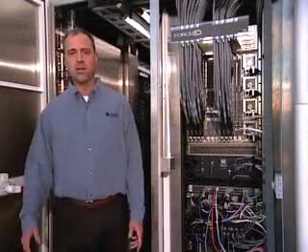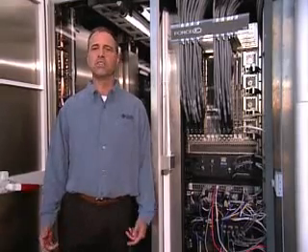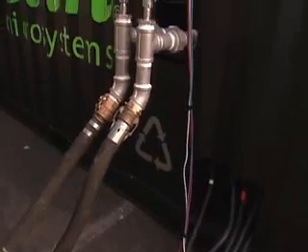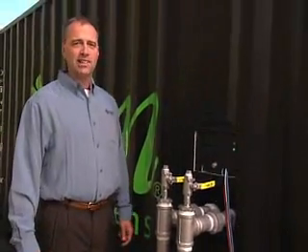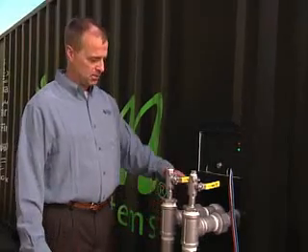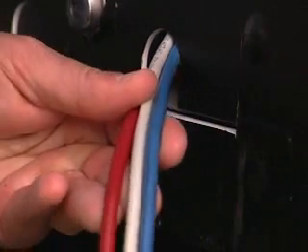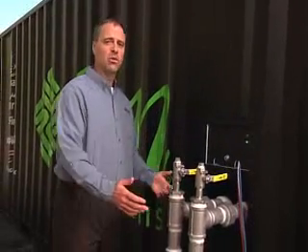So you might be asking, how hard is it to hook this up and get it up and running? Well, that's pretty simple. What does it take to get a Project Black Box online? We've got cold water and hot water that we hook up to a chilling system. We have standard Ethernet for networking, and standard 208-volt three-phase power to power the unit. That's all it takes. We deliver one of these into your site, you hook those up, and you're up and running.